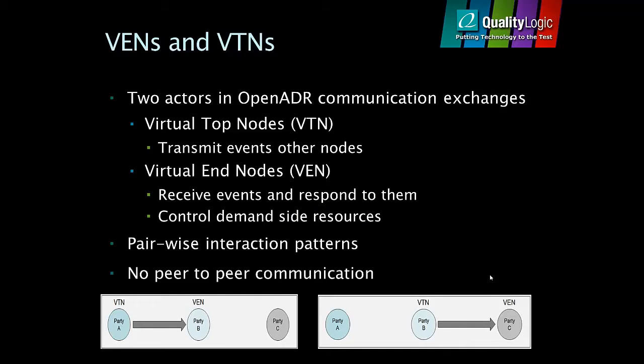There are two actors in OpenADR communication exchanges. The first actor is a virtual top node, referred to as a VTN. The VTN's role is to transmit demand response events to other nodes. The second actor is a virtual end node, referred to as a VEN. The VEN's role is to receive demand response events, respond to them, and to control demand-side resources. All communication is between pairs of VTNs and VENs.